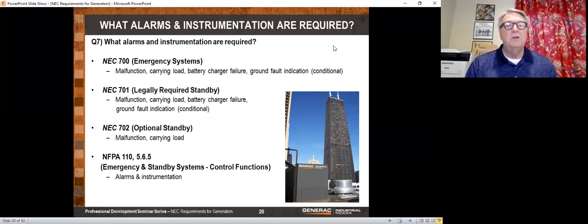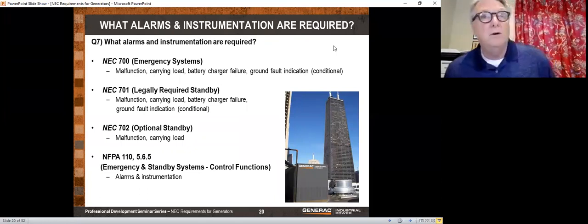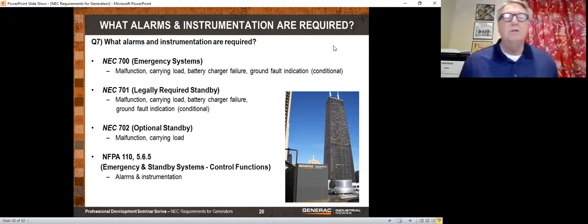What alarms and instrumentation are required? Well, let's talk about emergency first. You've got to have a malfunction alarm. I think of the malfunction alarm as kind of the engine check light. When that engine check light comes on, you're always unhappy because it's telling you something's wrong, but it's not telling you what is wrong. And all generators will have a malfunction light. In some cases, it's just a light or a buzzer and it tells you there's a fault, or an alarm. In other cases, with more sophisticated controllers, it will actually tell you what it is that's wrong. Carrying load, well, what does that mean? In general, that's on the transfer switch.